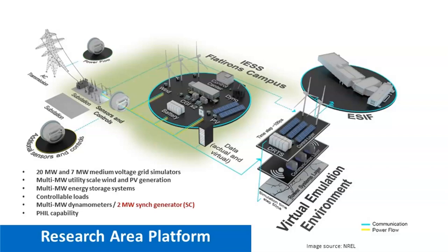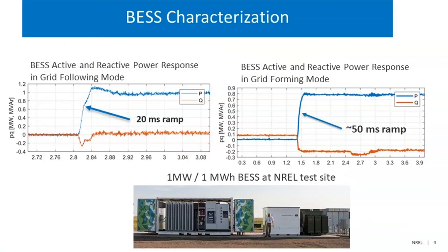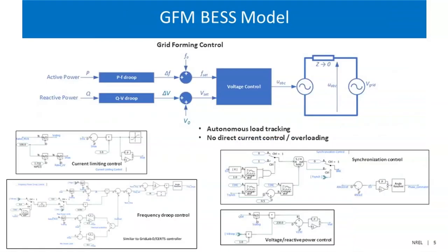So we're using this setup to do characterization of individual technologies. This is one example of active and reactive power of a battery in both grid following and grid forming modes. And we use this type of test results to validate our models for both dynamic and transient studies. So one example of how it's done, this is a simplified model of a grid-forming battery model that we're using for large-scale integration studies. The advantage of grid-forming, of course, is that grid-forming is absolutely necessary when we're talking about high-penetration grids because someone needs to set voltage and frequency.